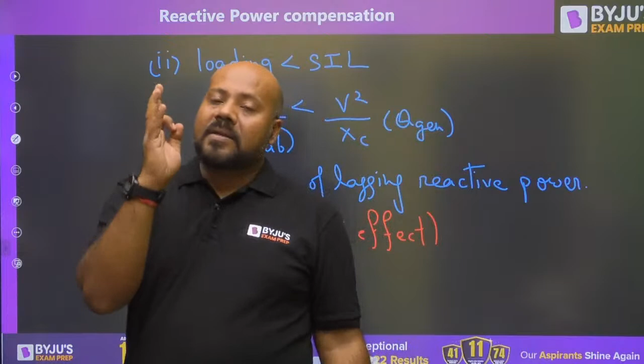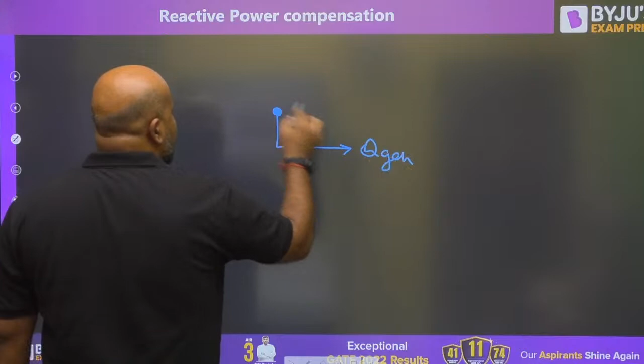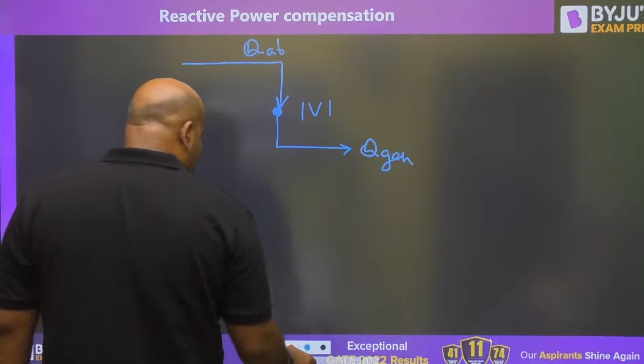And let me tell you a very simple classical concept. What is the classical concept? Suppose this is a node in your system. You understand what is a node in your system? Where two or more network branches are connected, that is what we call a node. Now suppose the reactive power generated is this and the reactive power absorbed is this. And suppose this is the voltage. So we have three conditions. Number one, if the reactive power generated at this node is more than the reactive power absorbed, the magnitude of the voltage of this node is going to be increased. If the reactive power generated is less than the reactive power absorbed, then the magnitude of the voltage of this node is going to be reduced. And if the reactive power generated is equal to the reactive power absorbed, then the magnitude of the voltage is not affected.